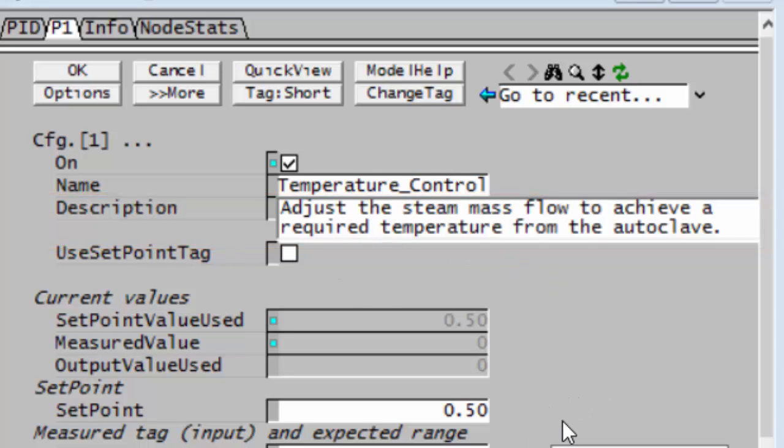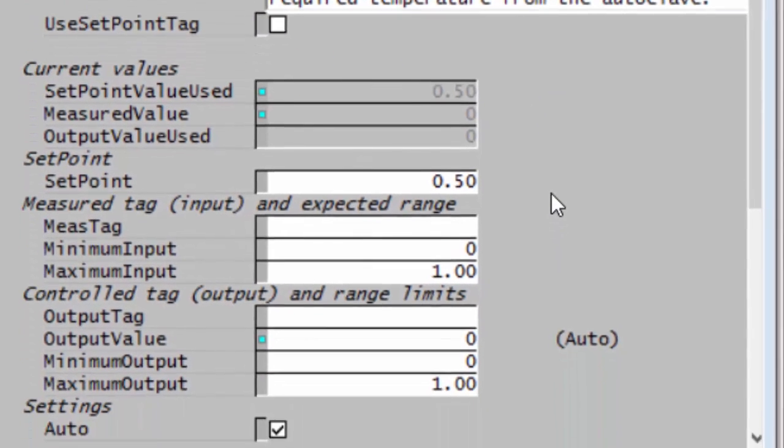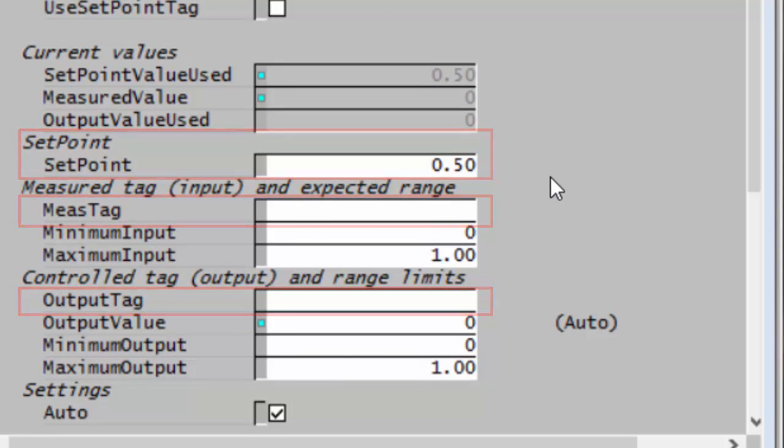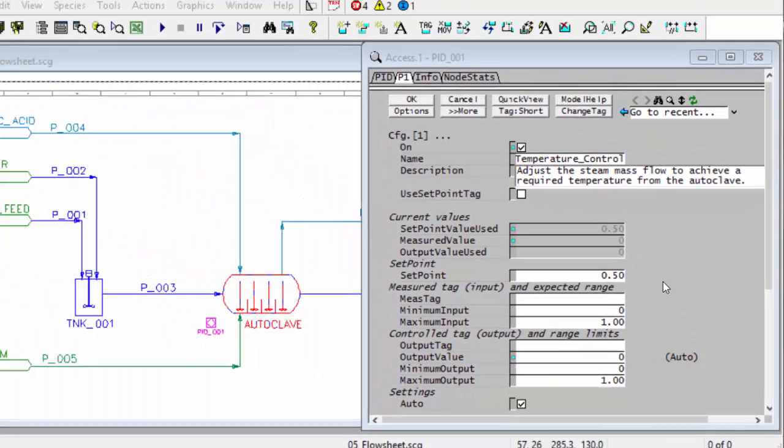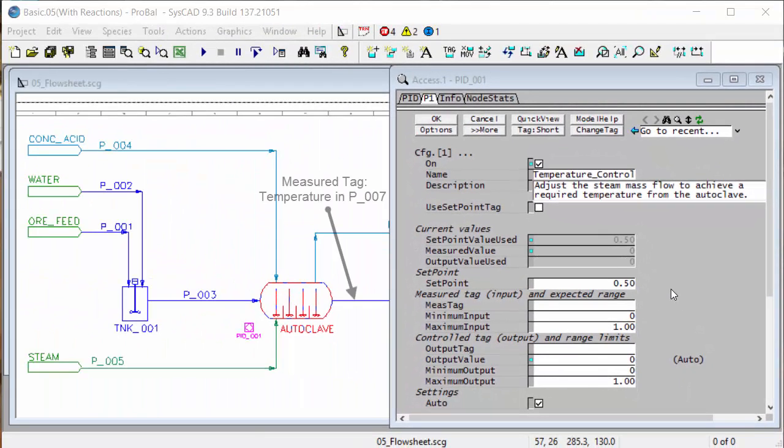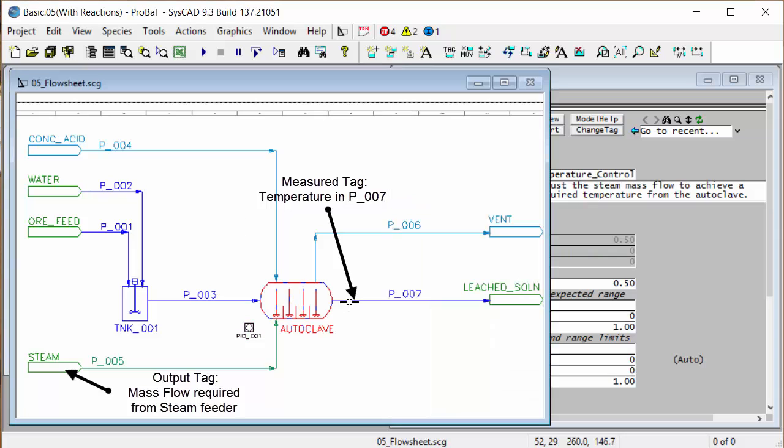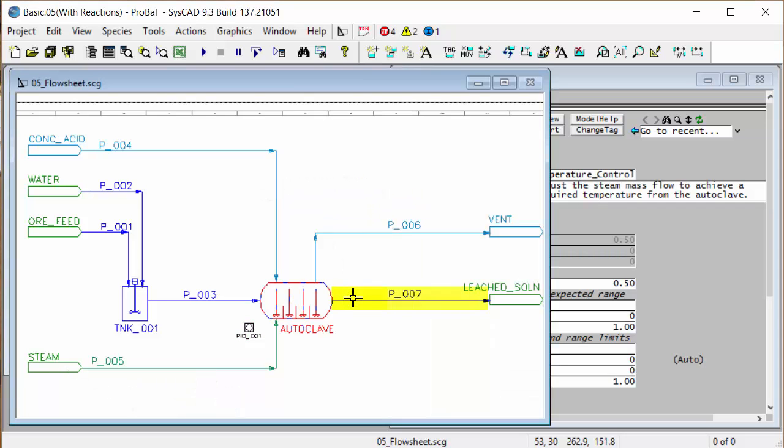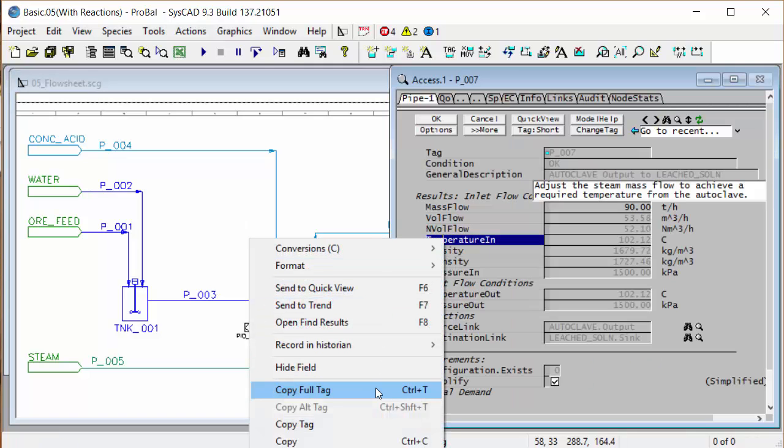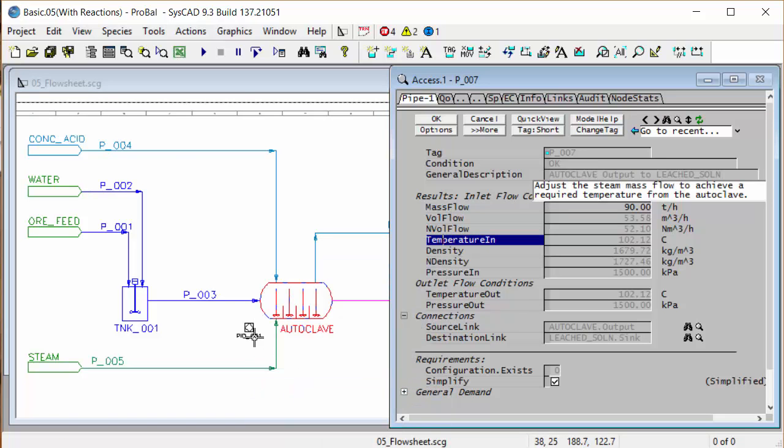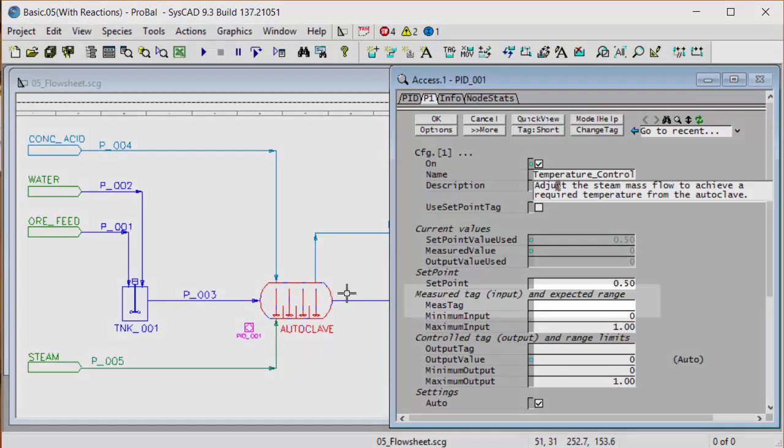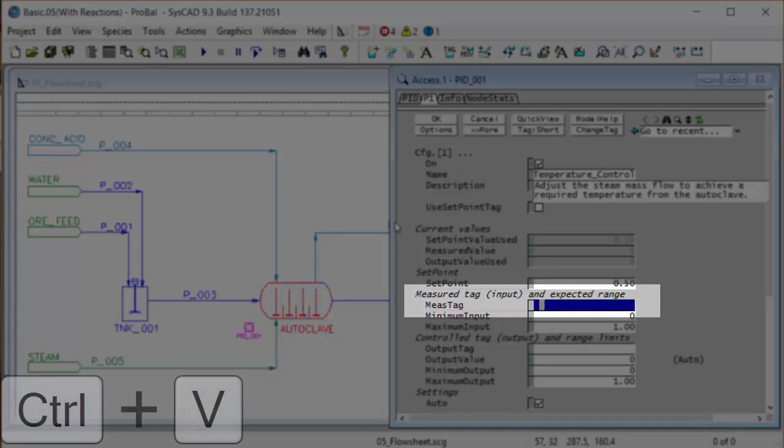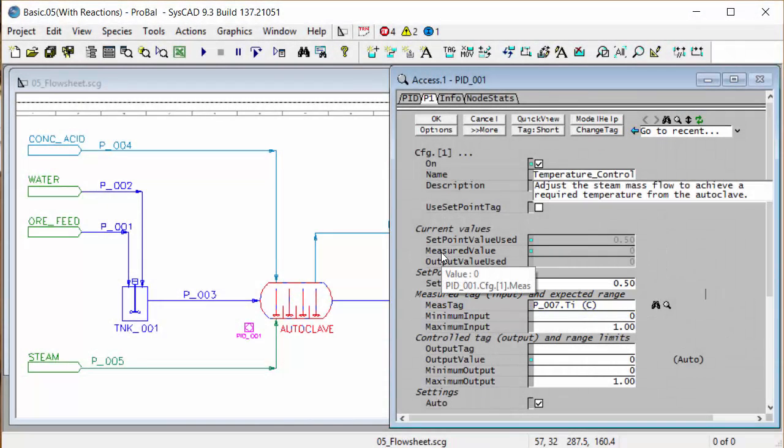The important ones to fill in now is the set point, the measured tag and the output tag. The measured tag will be the temperature coming out of the autoclave and the output tag will be the steam mass flow. So our measured tag, if I right click on the pipe coming out of the autoclave, P_007, and I want to measure the temperature. I'll right click on that and say copy full tag, then right click on my PID and paste that into the measured tag field. I'll say control V, click on the OK button to accept that change.